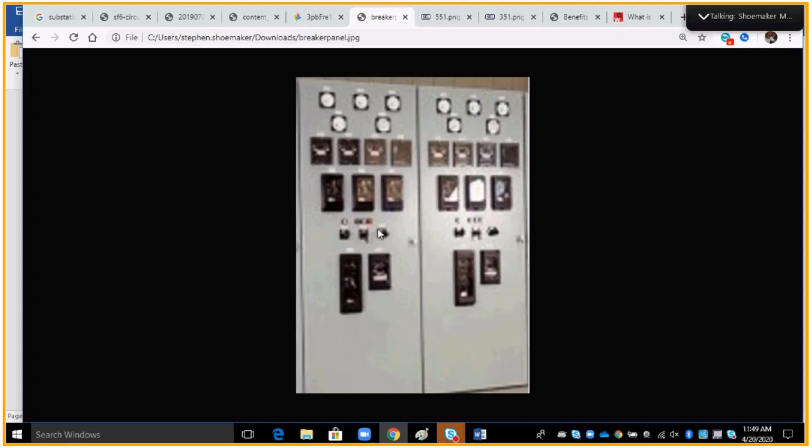In remote, SCADA has control of the breaker, of everything that it does except for one item. That is open. If you have an emergency where you're there at the substation or for some reason SCADA is down and you're not getting communication to that breaker, for safety reasons you can go straight to the breaker and turn this to open. The green light will come up. Remember, this is not a visual open, but this will take power off the entire circuit.